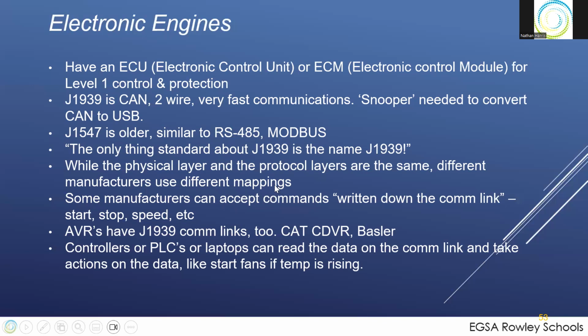And we have CAN bus mapping that goes on. We used to joke around and say the only thing standard is the name, 1939, because the mapping can be different. For example, you can't send a start signal down the communications link to a CAT unit. You have to have a hardwired start-stop signal going to the ECU to get a CAT to run. A Volvo will not accept a digital contact start-stop. Everything must go through the communications link. So different manufacturers have taken individual approaches on how they implement their control system. You can't just say one box does all, because sometimes you have different engines involved. So you have to know what those are in order to implement these.